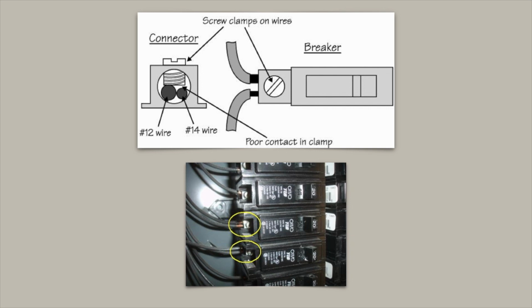A double tap is defined as 2 branch circuit wires installed in one circuit breaker. This is a safety hazard and a defect, because the 2 wires will micro-arc and cause the breaker to fail. The early failure of a breaker defeats the purpose of having a breaker protect the circuit. This is a fire hazard. Some breakers are designed for double taps, but that can't be determined without removing the breaker from the box, which is beyond our SOPs. Write up all double taps as a safety hazard unless you can clearly see the double tap icon.